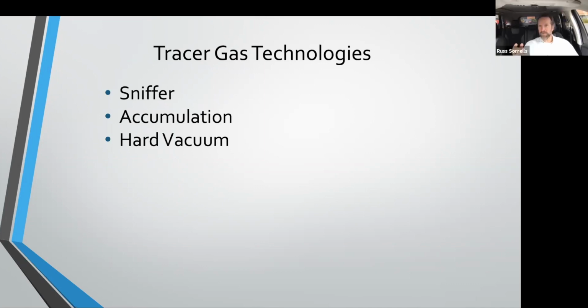So that's a great point. You put it underwater. Like how many years is it going to take for a bubble to develop on some of the stuff underwater, right? Exactly. So if you look at the refrigeration industry, they express their leak rate as 1/10 of an ounce of the refrigerant per year. If you look at air conditioning, it's typically 1/2 ounce of the refrigerant per year.